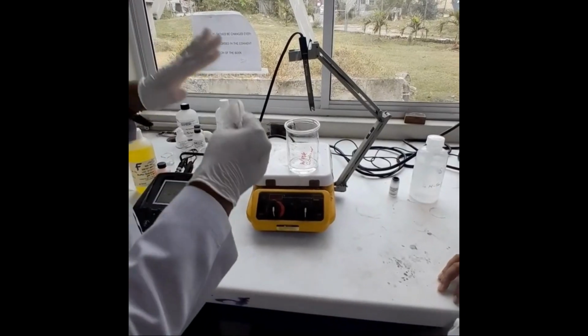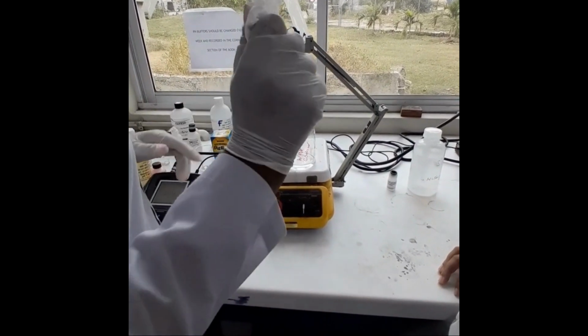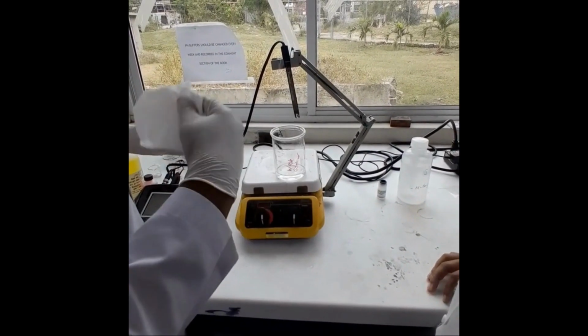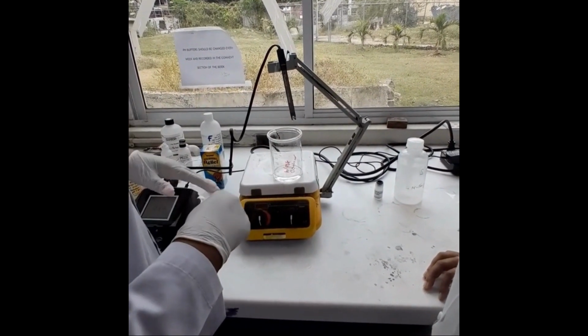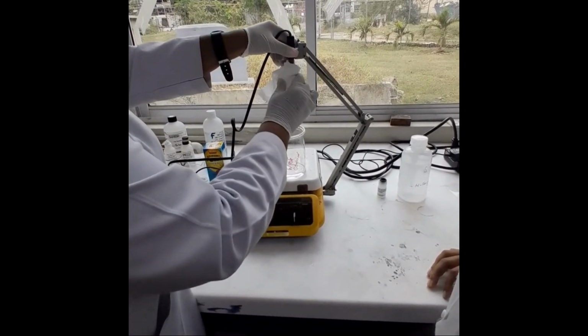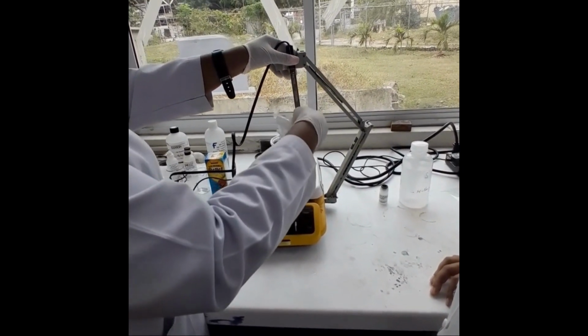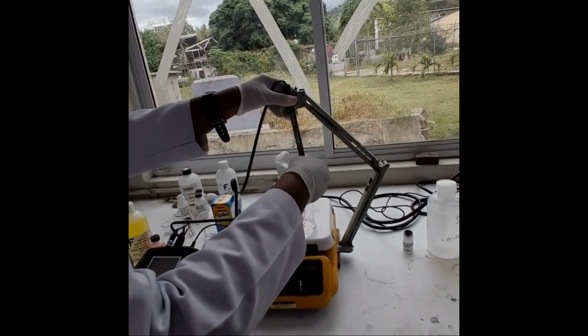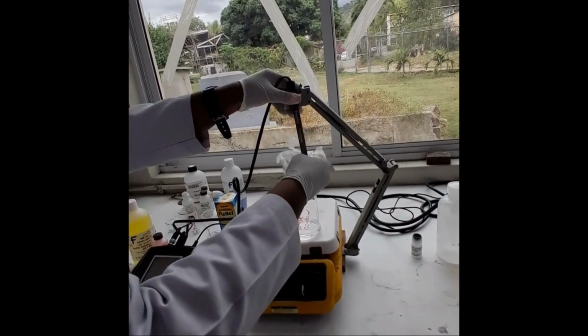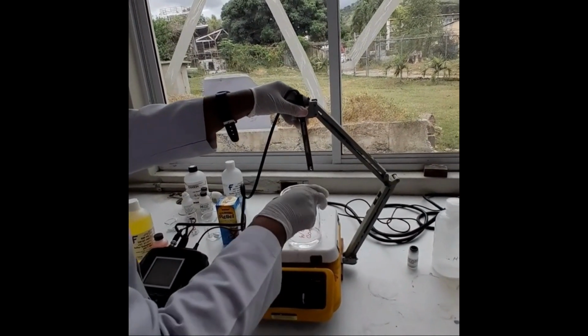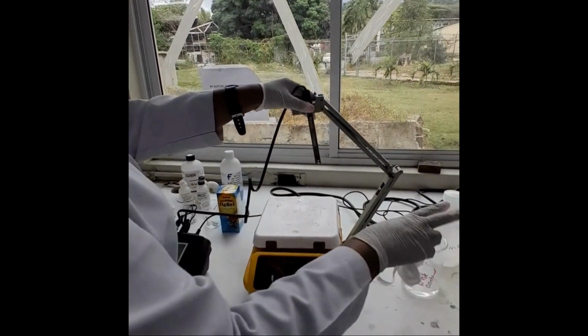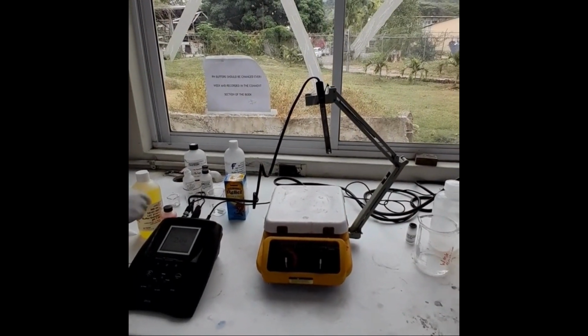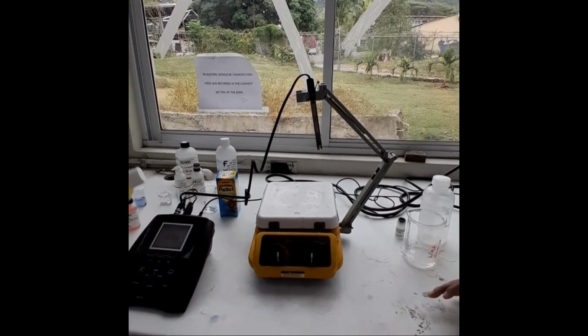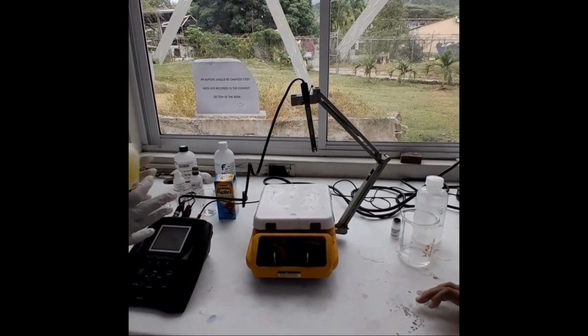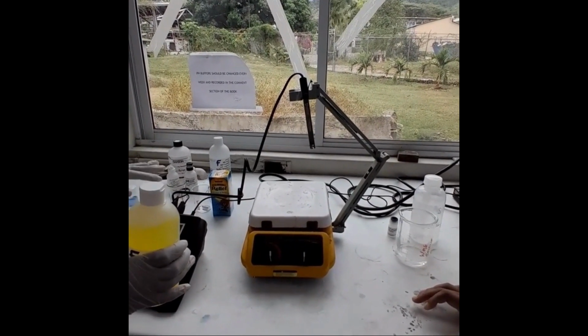So you want to blot dry your pH electrode with a soft tissue paper. You don't want to use anything rough that could disturb the surface of the pH probe. So you wipe down the sides and slightly tap the bottom. So that's it for cleaning the pH meter. You remove your pH storage solution. Next, we're going to start with buffer 7. You can start with whichever buffer you want, but I'll start with 7 for this demonstration.